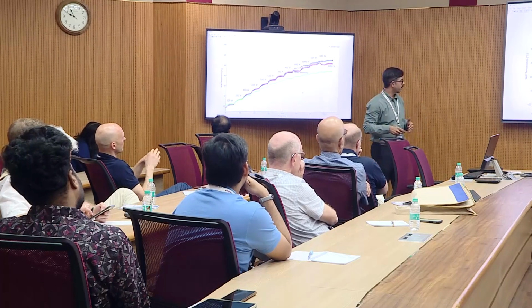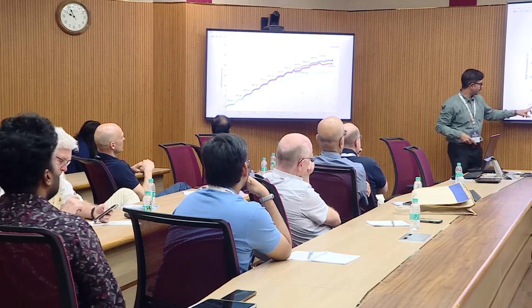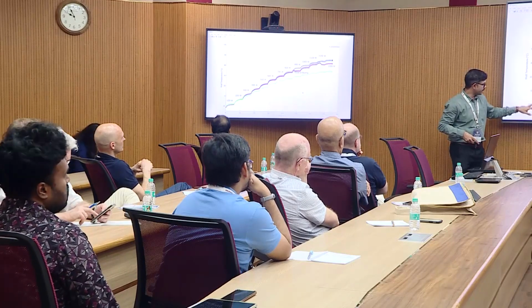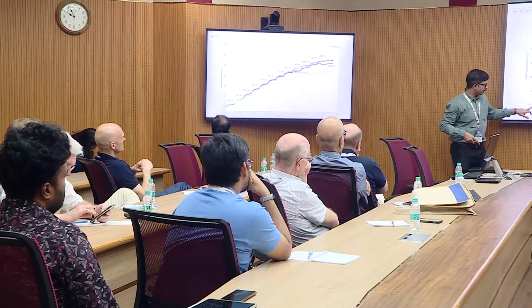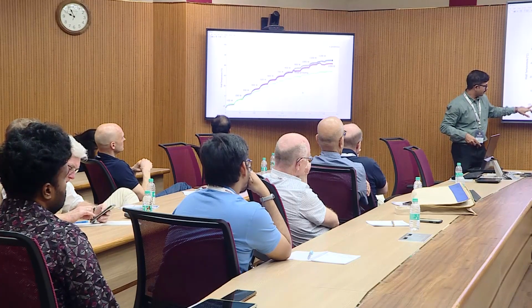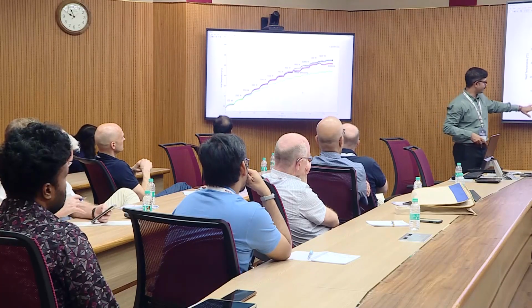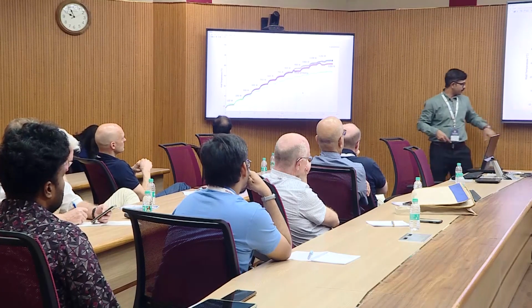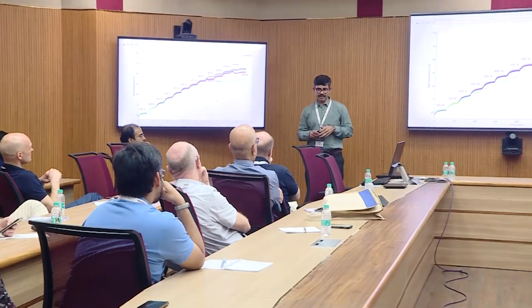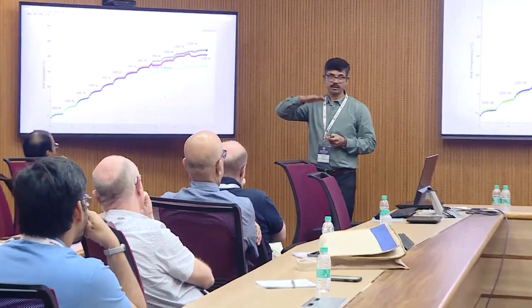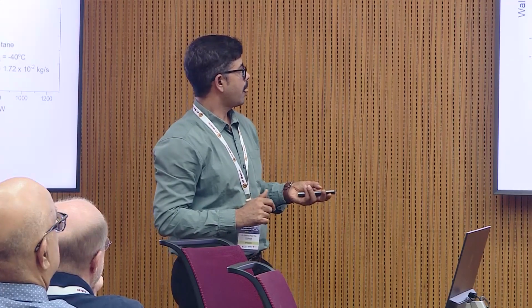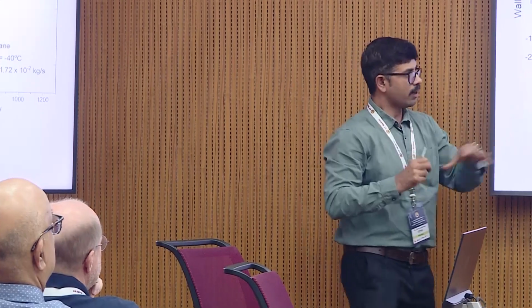But why is it higher than the evaporator? If you heat in the evaporator and you cool in the condenser. Yes, because initially this is at... I think there is a small difference. No, this is the evaporator temperature and this is the condenser temperature. Actually, what happens is initially, before giving the heat load, when it comes to ambient, okay, -20. Initially, almost they are at the same temperature. They are not much different, but there is a slight delta T between the evaporator and the condenser.